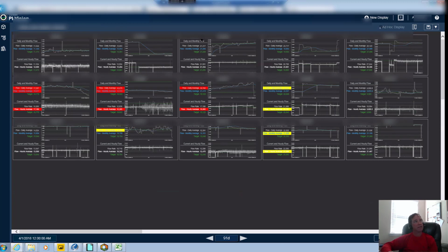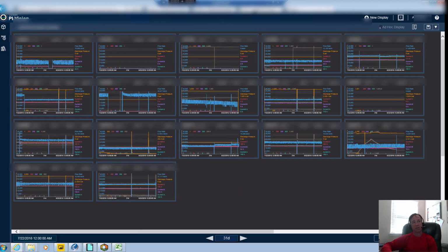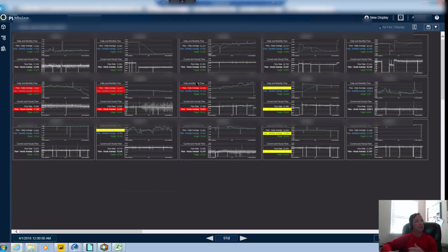But visually, instead of having to interpret all of these signals and not really know what's good and what's bad, here I can take a very quick look and say, you know what, I know what is happening here. Is this something I need to deal with? If you look, you can see this downward trend. You're like, well, there's definitely something going on. This could definitely be a leak. And we looked at this, and this was a couple of months of potential time that the customer could have saved in knowing they had a leak.